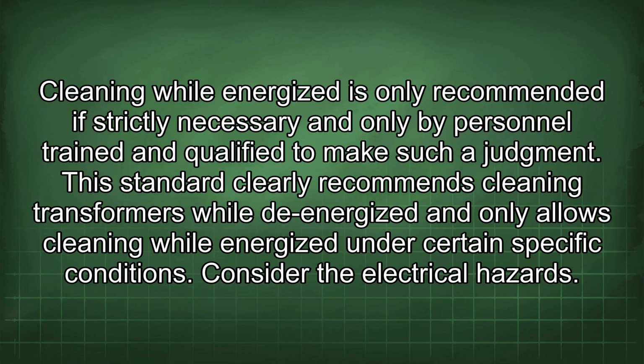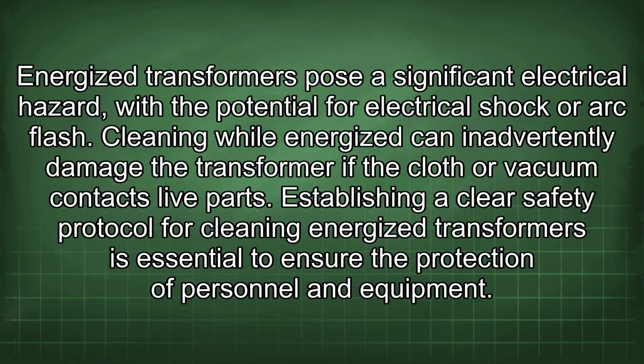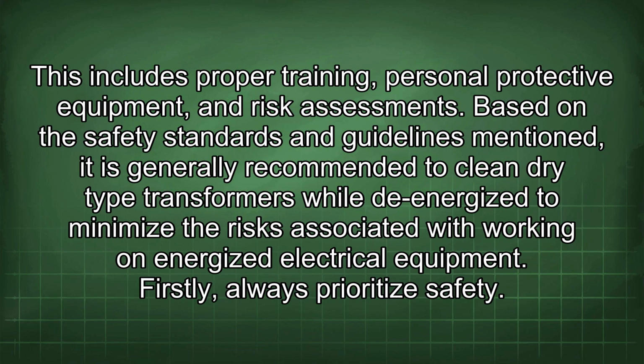Consider the electrical hazards. Energized transformers pose a significant electrical hazard, with the potential for electrical shock or arc flash. Cleaning while energized can inadvertently damage the transformer if the cloth or vacuum contacts live parts. Establishing a clear safety protocol for cleaning energized transformers is essential to ensure the protection of personnel and equipment. This includes proper training, personal protective equipment, and risk assessments. Based on the safety standards and guidelines mentioned, it is generally recommended to clean dry-type transformers while de-energized to minimize the risks associated with working on energized electrical equipment.